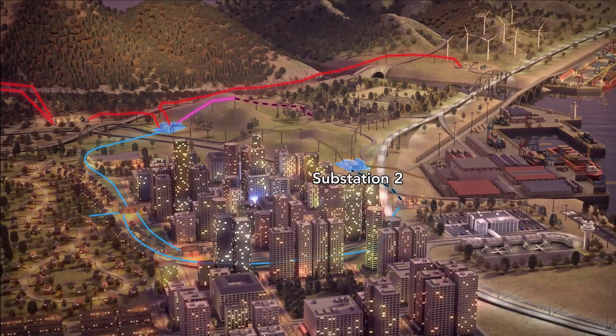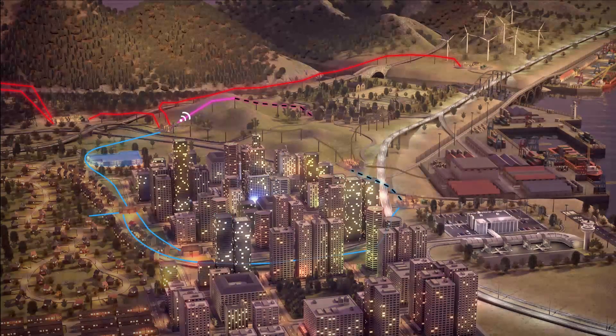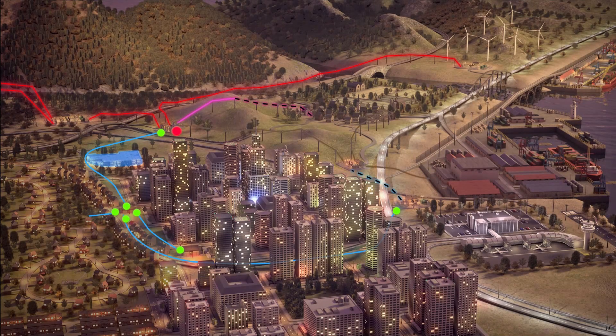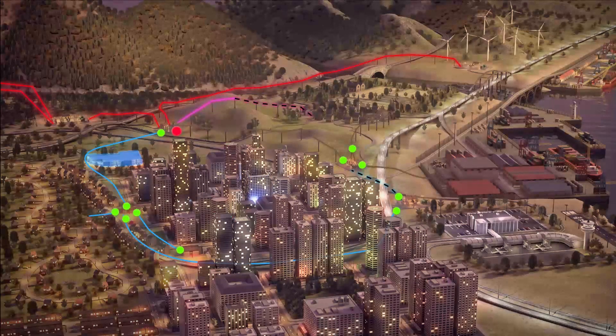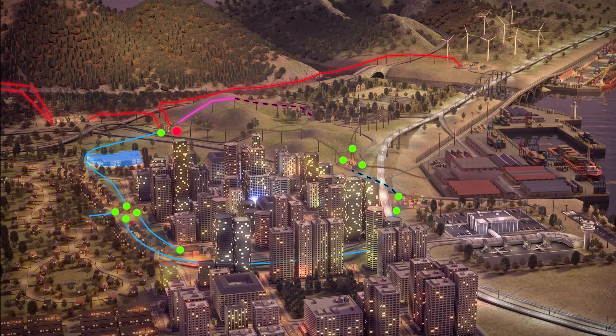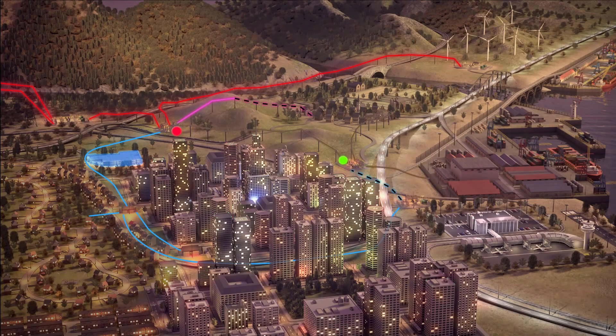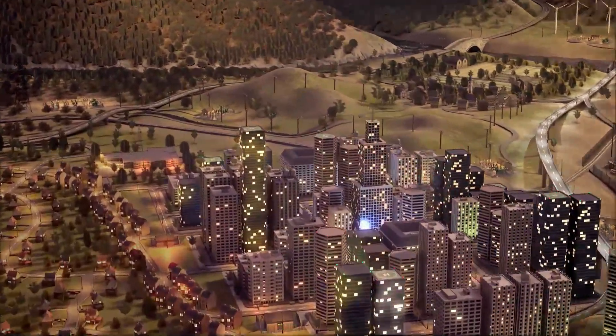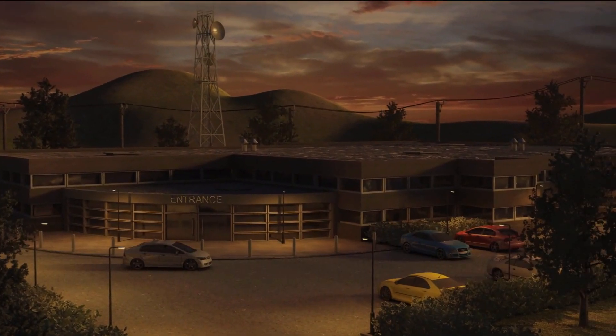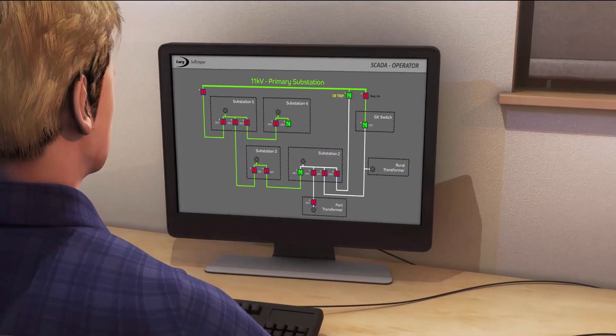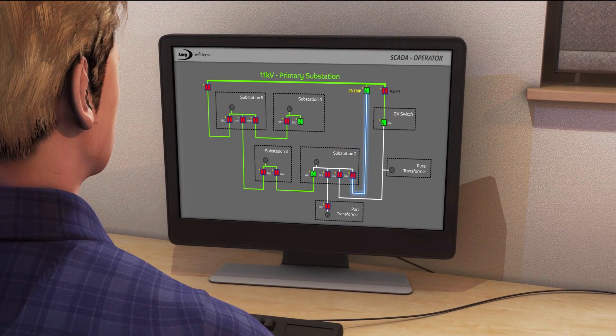Power to the rest of the network remains unaffected. The SCADA system receives notification of the circuit breaker trip, then uses the fault passage indicators positioned around the network to determine where the fault has occurred. In this case, the fault passage indicator at substation 2 has not tripped, so at the remote SCADA data centre, the operator is informed that the fault must be somewhere on the line between the primary substation and substation 2.